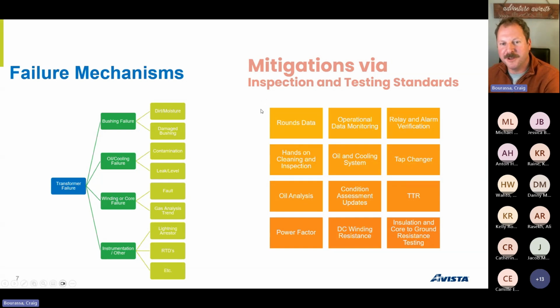That should really feed into your operations and maintenance work. Anything you do at your plant should be trying to mitigate some of these failure modes. You do daily rounds, look at oil levels to check for leaks, look at temperatures to see if you have a fault condition coming on or some instrumentation not working. For every asset class - generators, turbines, etc. - we go through this process and then write a standard for the maintenance.